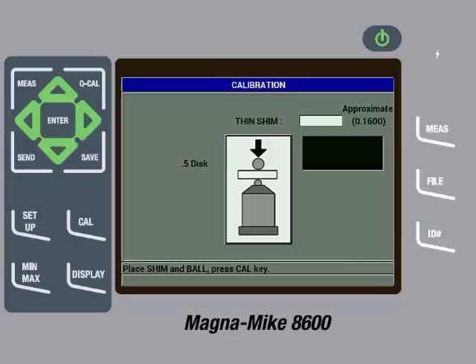The next step would be to insert the disc into the slot on the top cap of the thickness reference standard and then place the fixture on the probe tip. Then gently pull down on the sides of the fixture to ensure the shim is in contact with the probe tip. The instrument will start displaying a thickness value. Once the reading is steady, press the Cal key. Then use the arrow keys to input the precise thickness of the shim, which in this case is 0.160 inches or 4.064 millimeters. Then press the Cal key. We can then remove the disc target and calibration standard.